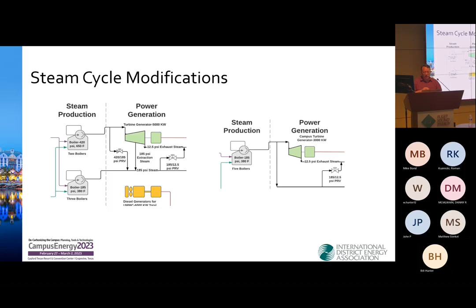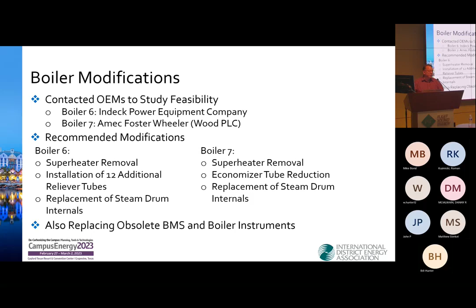Taking a boiler and reducing its pressure is not a simple thing - you have to get a hold of the OEMs, get their buy-in, and redesign because you have to change the internals of the boiler. Luckily, even though we had one of the boilers from 1968, we contacted the OEM, they went to their file cabinets, found the drawings, and we got a study done. It was feasible and we moved forward. Boiler 6, the one on the left, was completed and is now operating at the new pressure. Boiler 7 starts next month.